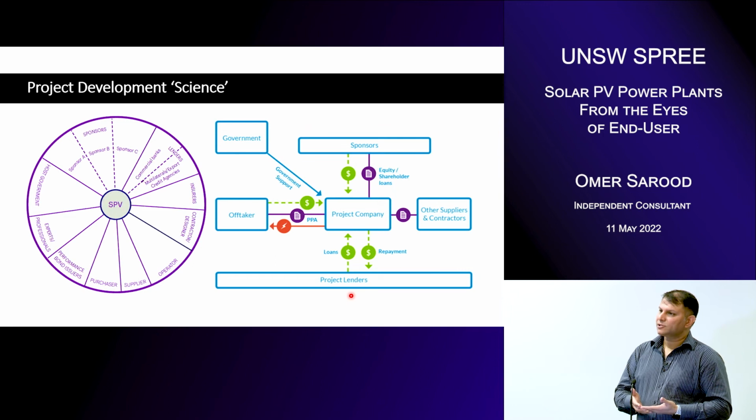Yes, exactly. That's a very interesting question. Well, with the single axis tracker, you don't have a lot of structure to worry about from the backside, right? But if you want to put the bifacial modules in a fixed tilt environment, which I have not seen in a lot of projects from different companies, it would create problems for fixed tilt, but not for trackers, because with trackers you have a lot of space. Unless you go for the two portrait trackers, where you have slightly more structure, but still the amount of structure used in trackers for 1P or 2P versus fixed tilt is significantly different.